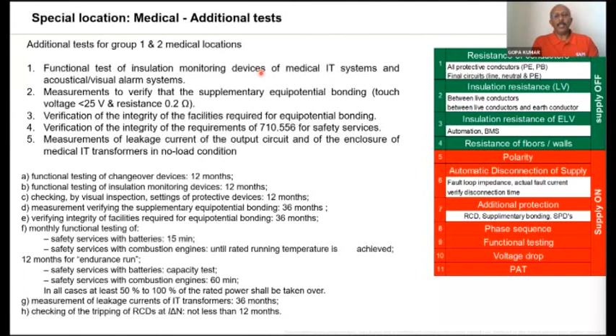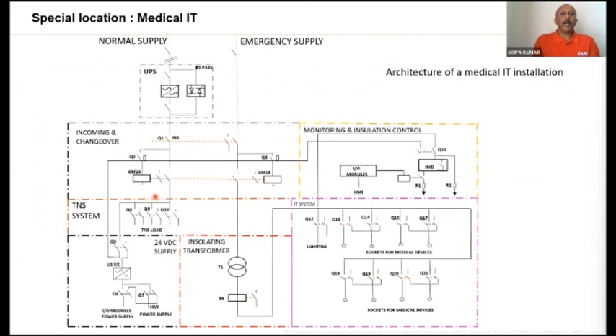There is an IS standard called IS 17512, which explains this particular subject, how to make additional tests in a hospital location or a medical location. So all these things are mandatory. But to tell you the truth, these 3 things: the risk assessment, a medical location where the risk assessment is made, where all the medical electrical equipment are conforming to the IS code or the IEC standard, plus tested as per this IEC standard, is really rare. It's the rarest in our country, unfortunately.